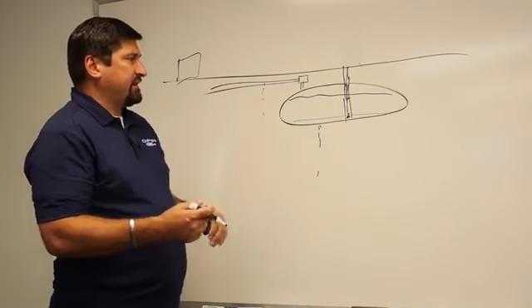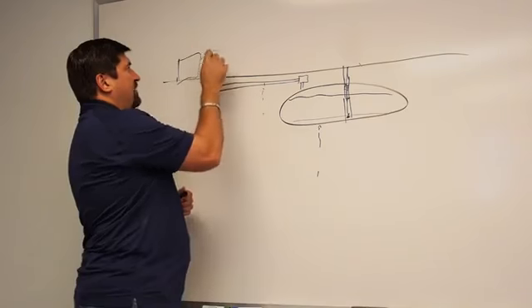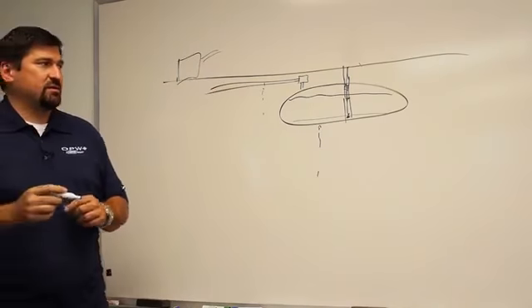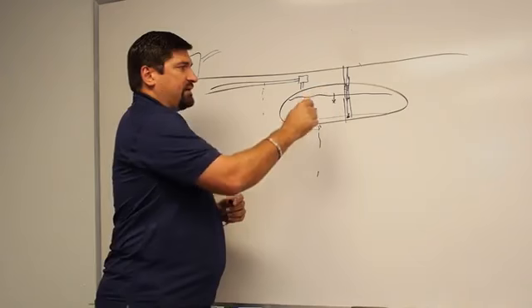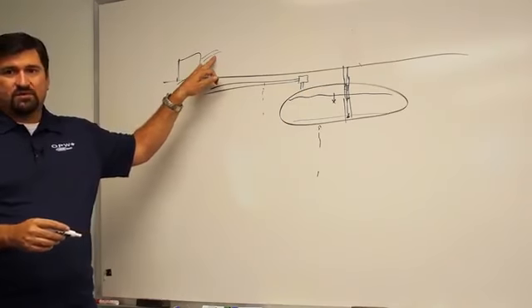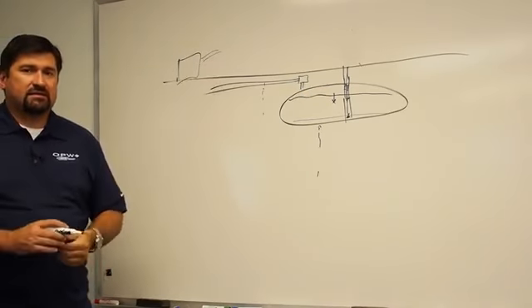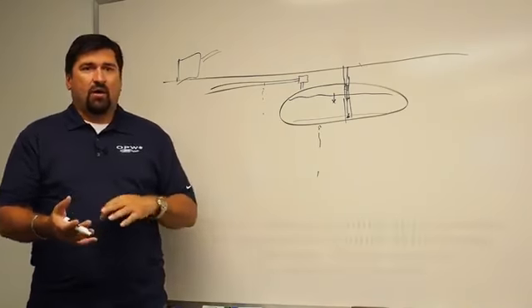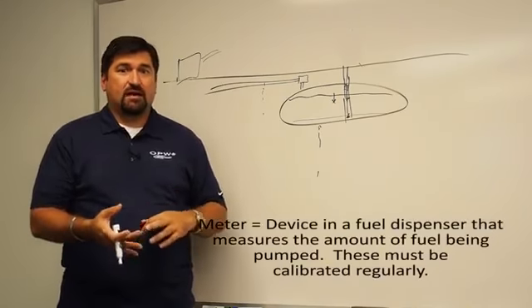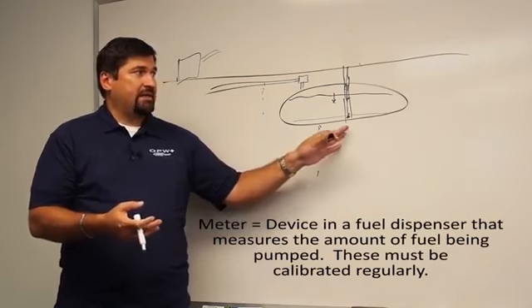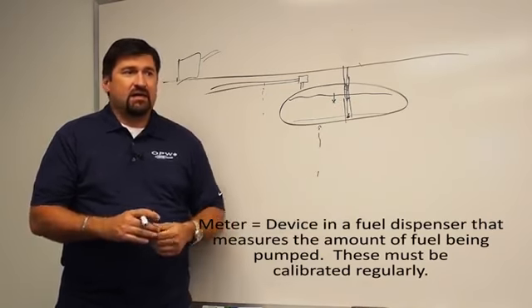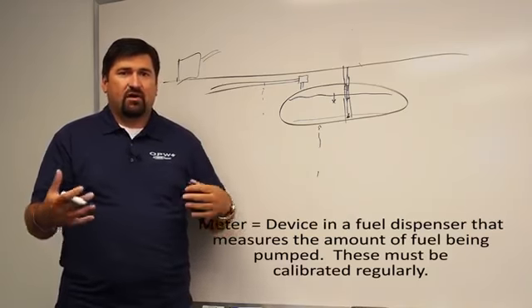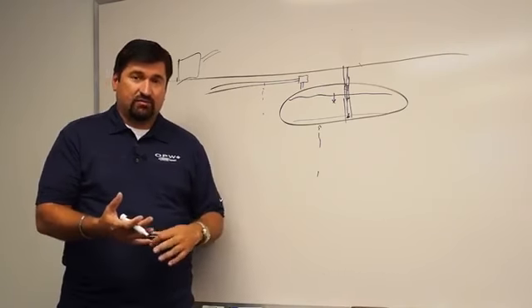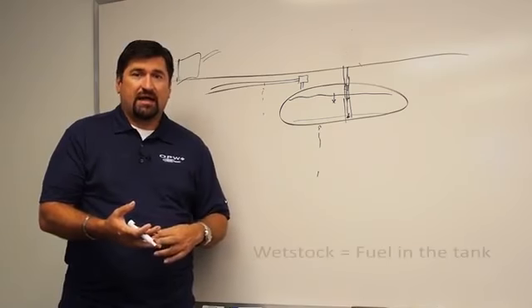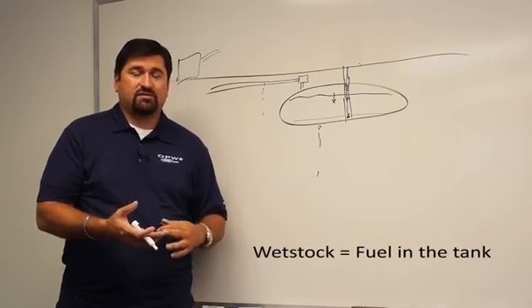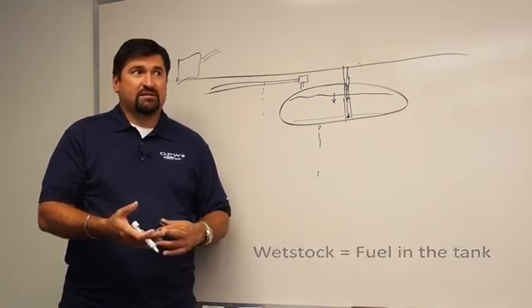Well, the other thing that the ATG is able to do is that it knows how much product is leaving the tank through a dispenser. So it looks to see if the product that fell in the tank matches what was dispensed, and this is their monthly reconciliation. And this will tell them whether or not their meters need calibration, or if somebody is actually stealing product out of the tank, just siphoning it right off the tank. So the implementation of an automatic tank gauge is designed to meet the regulatory requirements, tell them what they have as far as wet stock volume, and it also helps them monitor theft through reconciliation.